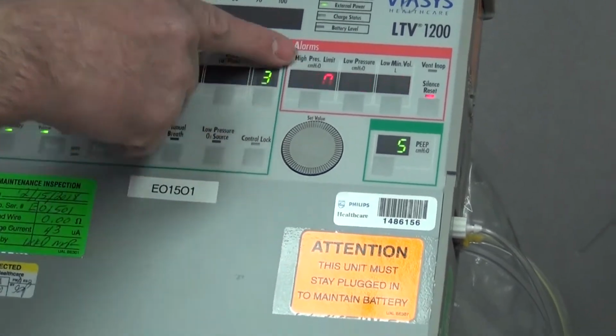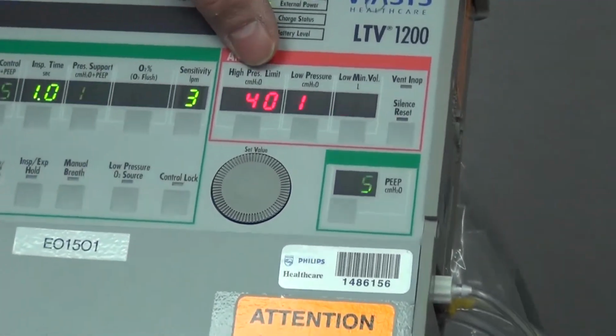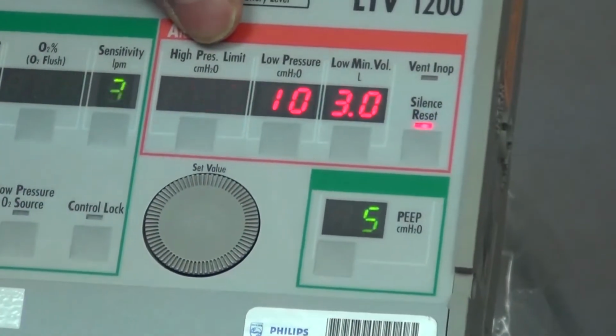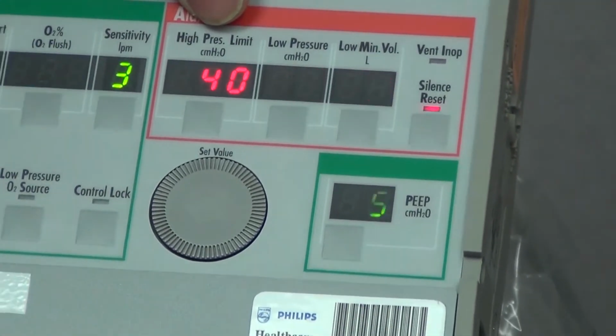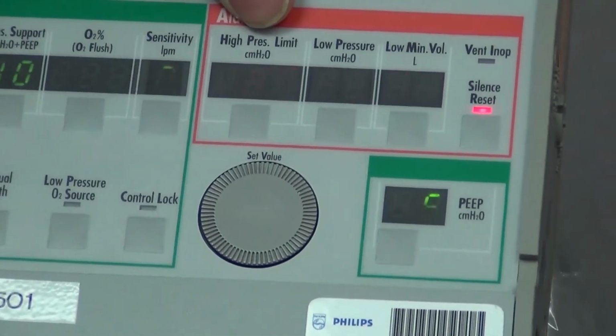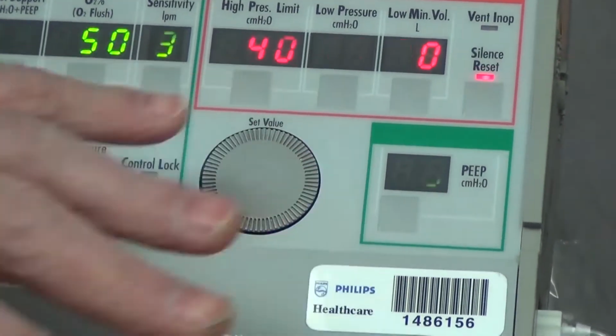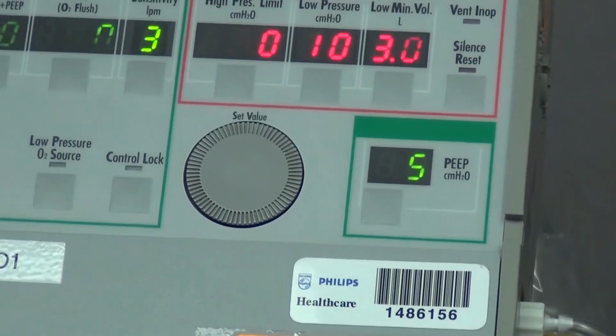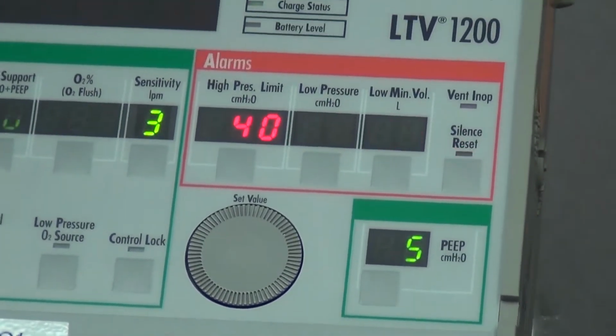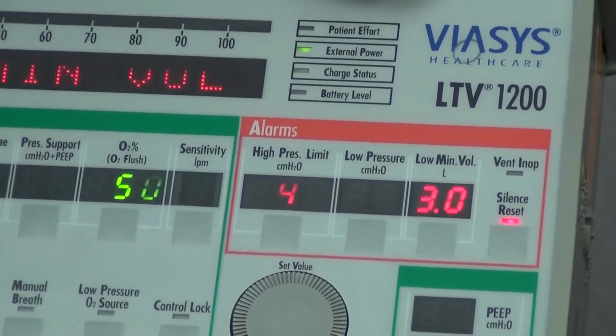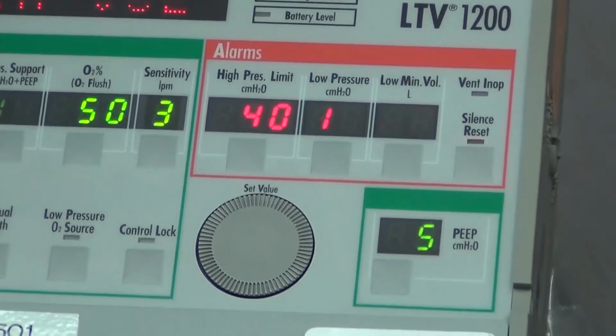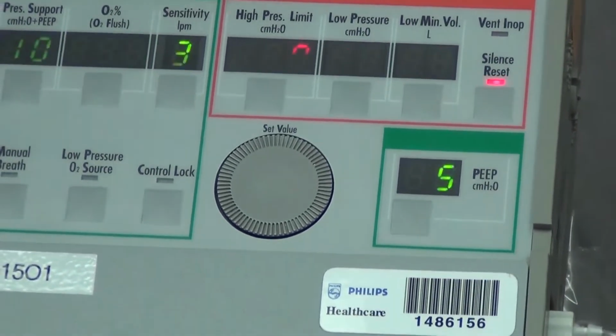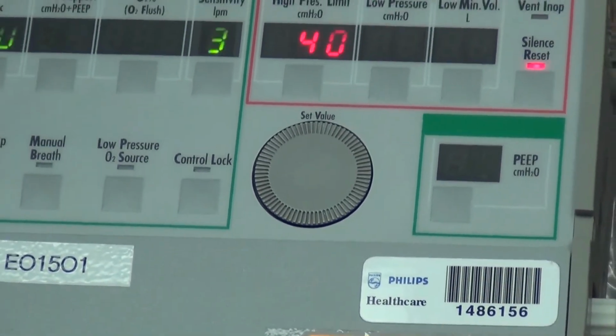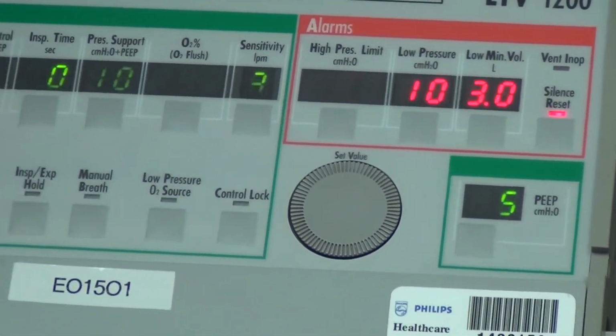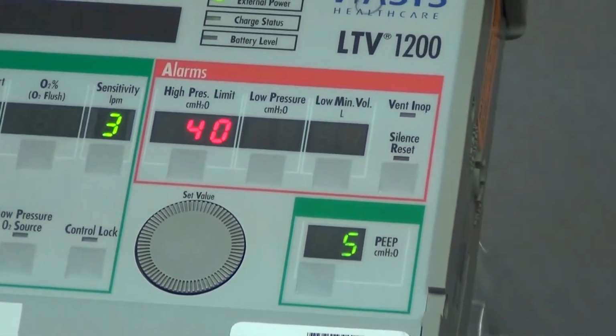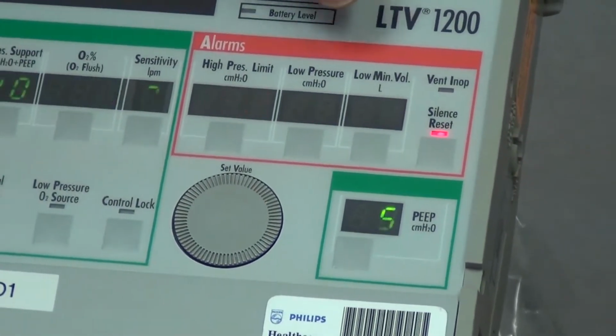If we look at the red box, the first one, it says high pressure limit or peak pressure limit. We want that to be a safe level, and like the other ventilators, a good place to start is 40. So when you start this, typically it'll be on 40. If you inflate patients with a pressure higher than 40, you may risk to pop a lung, create a pneumothorax, and that could be a safety thing. So this will limit the machine to not exceed the pressure of 40.